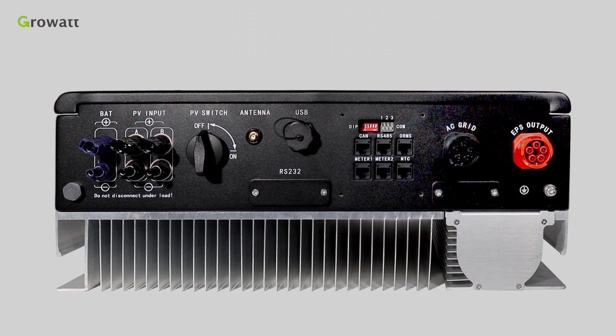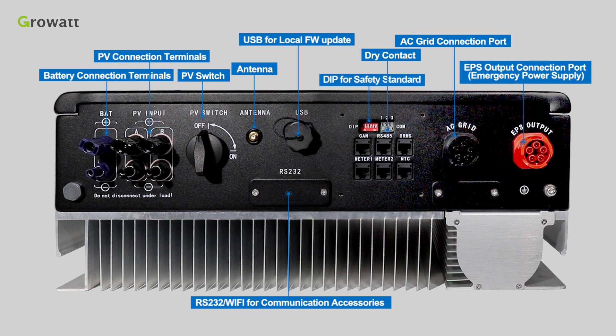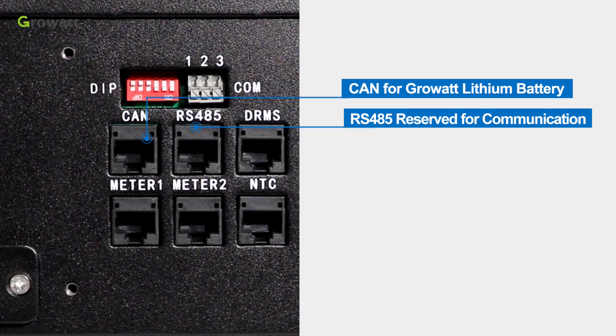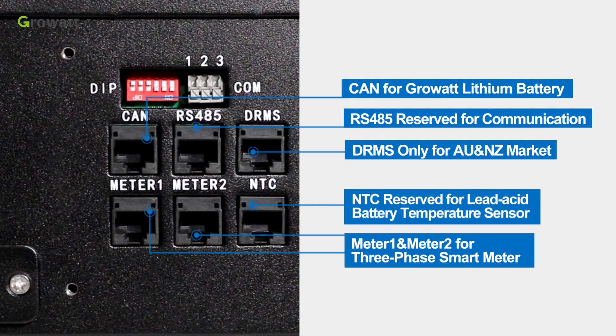There are some connection terminals including battery connection terminals, PV connection terminals, PV switch, antenna, USB for local firmware updates, RS-232, Wi-Fi for communication accessories, DIP for safety standards of different countries, dry contact, AC grid connection port, EPS output connection port for emergency power supply. Communication terminals include CAN for Growatt lithium battery, RS-485 reserved for communication, DRMS only for Australia and New Zealand markets, meter 1 and meter 2 for three-phase smart meter, and NTC reserved for lead-acid battery temperature sensor.